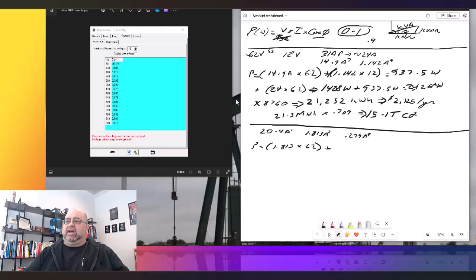Now this is literally within 2 hours. So we took the measurements before shutting down any equipment, shut down the equipment, put the harmonic filters in, well actually there's a number of them we put in, but we put in the ones across ground and then restarted, so about 2:30 to 4:30, and then started back up, and then we took the readings about 5-ish after everything restarted and came up to speed. Cryptocurrency site, we had to wait for all the miners to get started again, which are immediately loaded. That was just amazing.